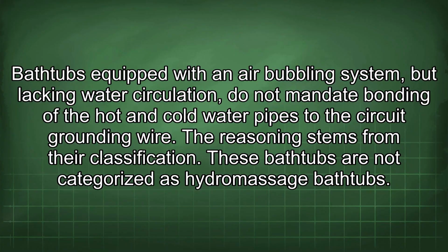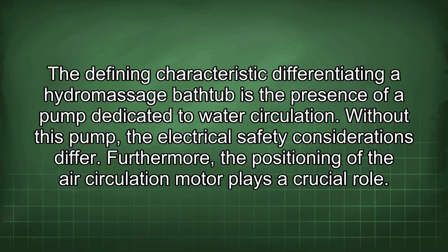Bathtubs equipped with an air bubbling system, but lacking water circulation, do not mandate bonding of the hot and cold water pipes to the circuit grounding wire. The reasoning stems from their classification. These bathtubs are not categorized as hydromassage bathtubs. The defining characteristic differentiating a hydromassage bathtub is the presence of a pump dedicated to water circulation. Without this pump, the electrical safety considerations differ.